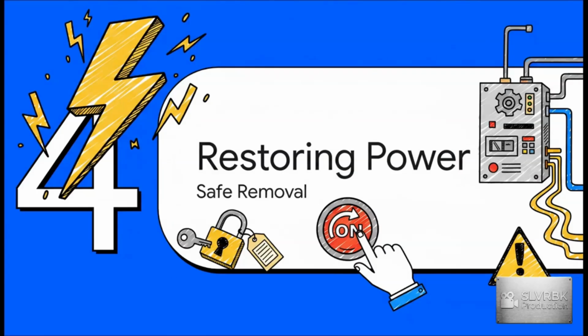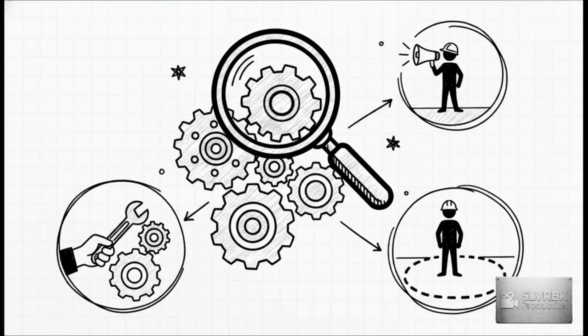Section 4. Safe removal and restoring power. Believe it or not, re-energizing a machine is actually one of the most high-risk moments of the entire process. Before removing devices, you've got to inspect the machine to ensure it is operationally intact and check to assure everyone is positioned safely away. It is extremely important that all employees respect lockout and tagout devices during this phase.